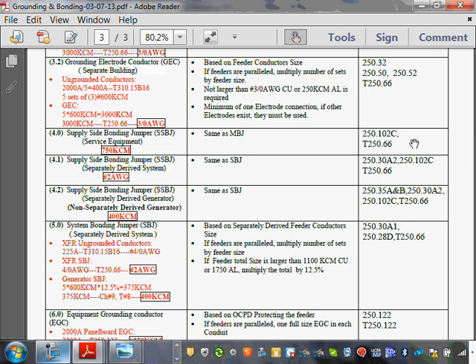I have my 5 sets that I already sized for the ungrounded conductor, 600 kcmil each. Multiply them by 12.5%, exactly like the supply side system bonding jumper or the main bonding jumper. These are the rules. And you get this number, 375. Do they make 375 kcmil in the industry? If you don't know, before you call somebody and ask for that size, go to Chapter 9, Table 8 in the NEC book, and it will go to the next standard, 400 kcmil.